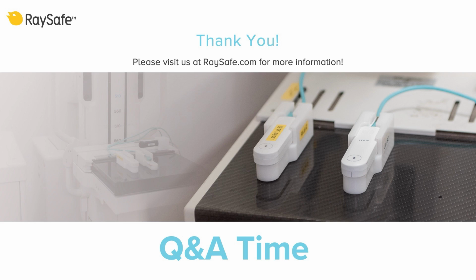How does the sensitivity change with the direction? Well, the 452 has quite a good energy or dose rate response all the way out to 90 degrees of the meter, but it varies depending on the energies which you are measuring. And there are very good pictures in the manual showing all the different angles and energies and so on. So I recommend going to the manual for all the deeper details when it comes to angular response.